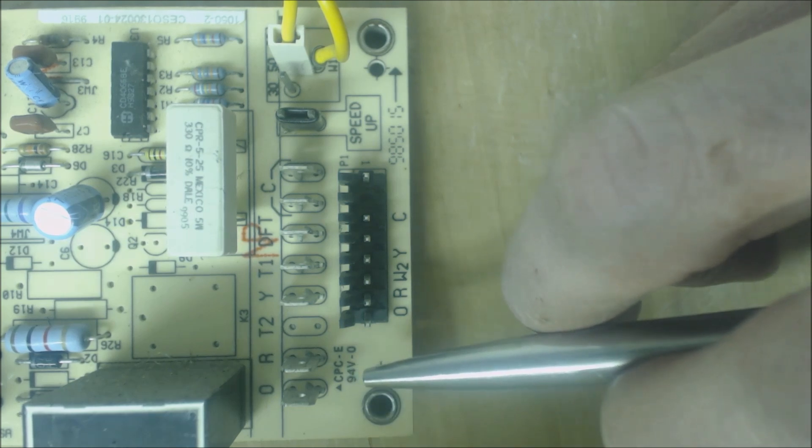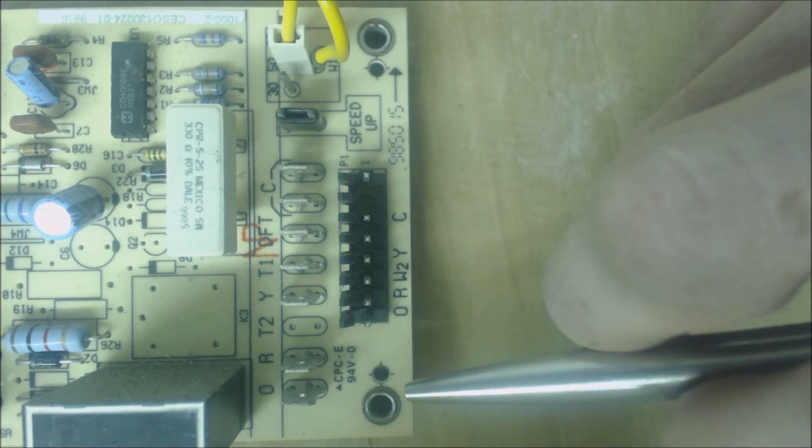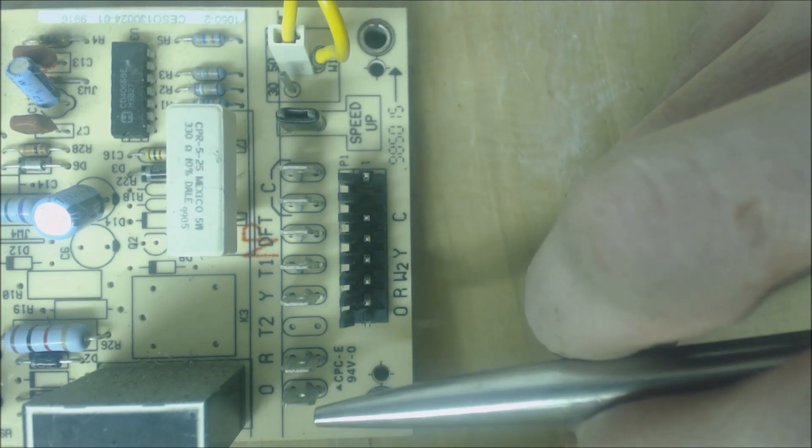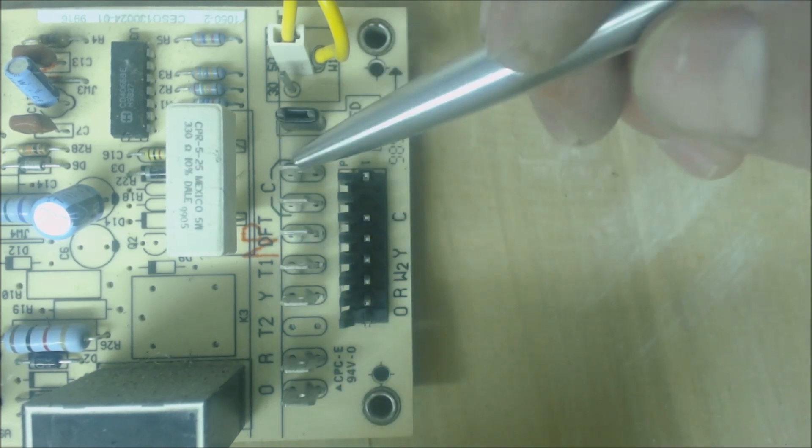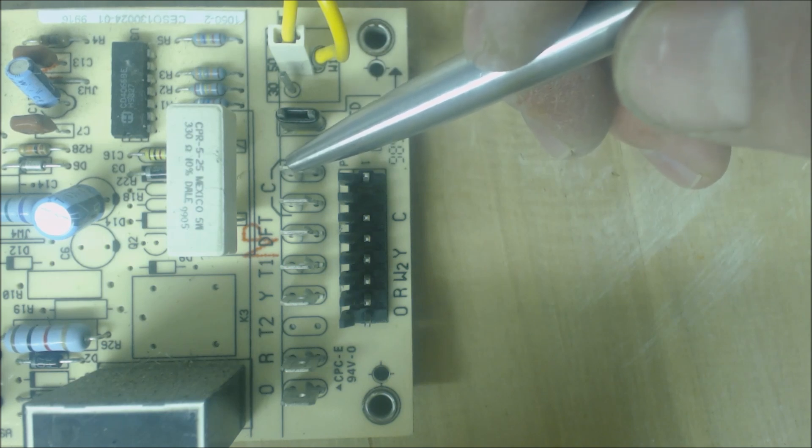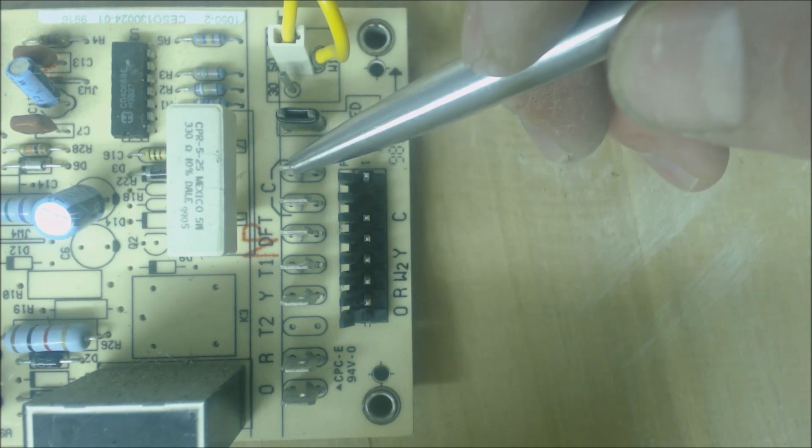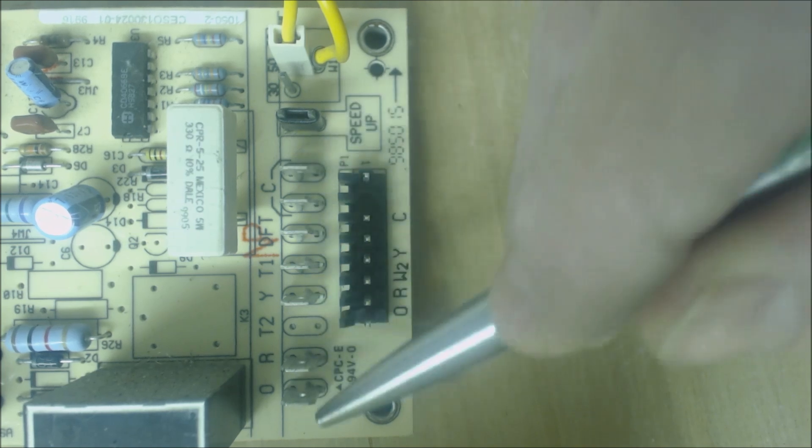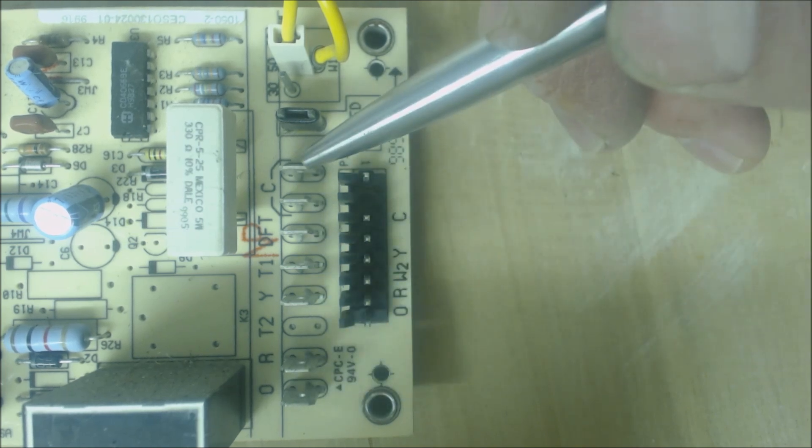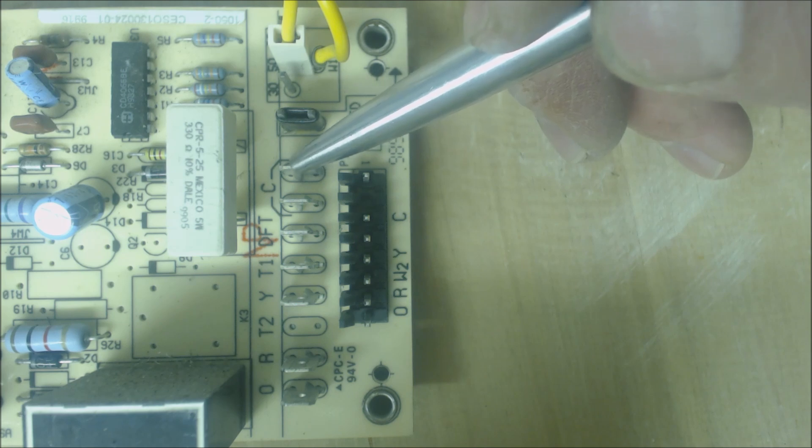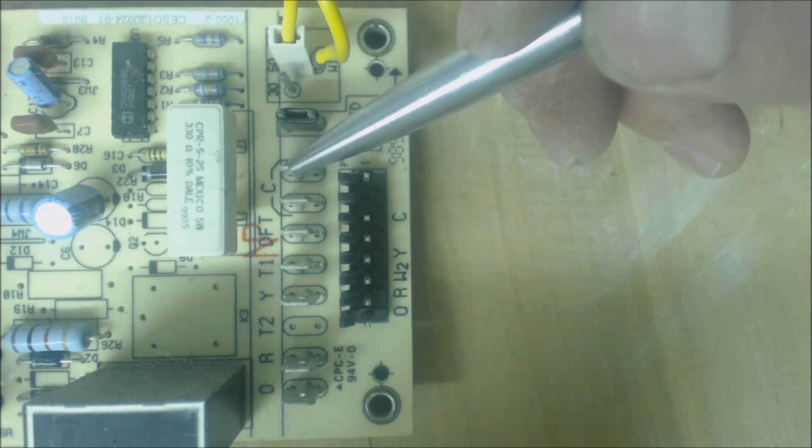And then you have O that powers the reversing valve, and then it comes back to the common. That happens during cooling mode from these two terminals here, and as well it happens during defrost, because during defrost you're actually running in cooling mode without the fan.